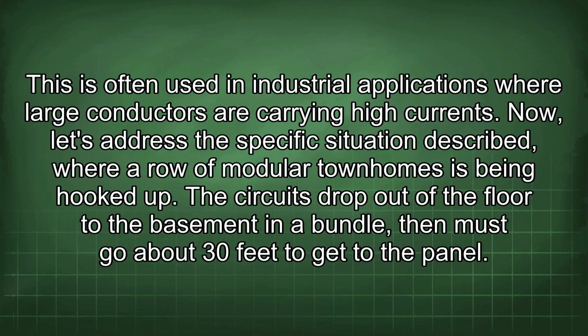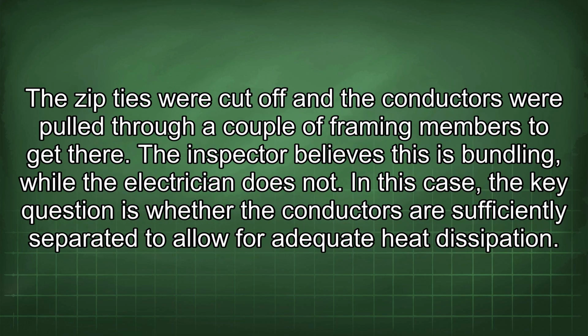Now, let's address the specific situation described, where a row of modular townhomes is being hooked up. The circuits drop out of the floor to the basement in a bundle, then must go about 30 feet to get to the panel. The zip ties were cut off and the conductors were pulled through a couple of framing members to get there. The inspector believes this is bundling, while the electrician does not. In this case, the key question is whether the conductors are sufficiently separated to allow for adequate heat dissipation.